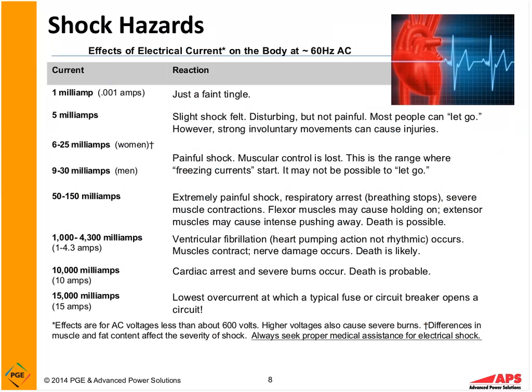So when we look at shock hazards, it takes very little current flow and very little voltage in many cases to cause that current to flow. With wet hands or cuts or scrapes on our hands, as little as 30 volts can cause enough current to flow to get us around 50, 60 milliamps of current flow, which we'll look at here. A lot of times, though, 120 volts, 277 volts are pretty common exposures that we work on in the industry, 480 volts. So you can see as little as 30 volts under the right conditions can cause issues. And by the way, OSHA and NFPA 70 generally look at the risk of injury. Generally about 50 volts is their threshold where they're really focusing on enough current to flow to cause some significant injuries.